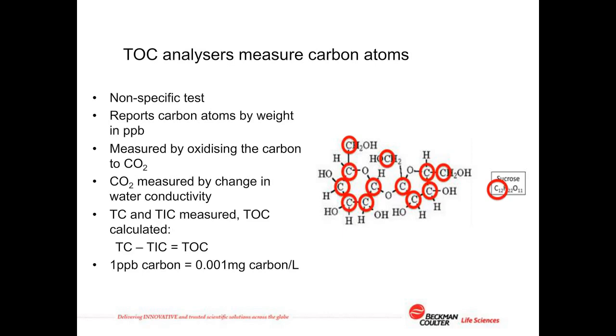The carbon atoms are released from the organic molecule by breaking the molecule down through the process of oxidation. The carbon forms into carbon dioxide, which in turn dissolves into the water to elevate the water's conductivity. Before the TOC is measured, the TOC analyzer must first measure the amount of carbon dioxide dissolved in the water already, and this is called total inorganic carbon. Then the organics present in the water are oxidized to release the carbon they contain, and total carbon is measured. By subtracting total inorganic carbon from total carbon, the levels of total organic carbon in the water can be ascertained.